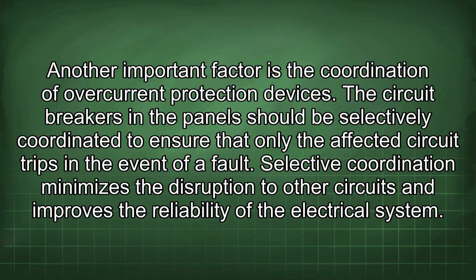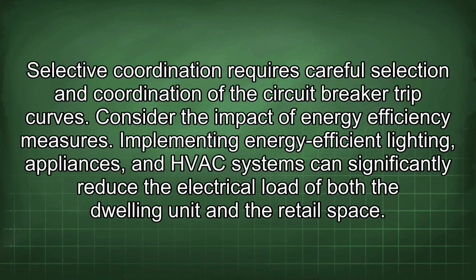Another important factor is the coordination of overcurrent protection devices. The circuit breakers in the panel should be selectively coordinated to ensure that only the affected circuit trips in the event of a fault. Selective coordination minimizes the disruption to other circuits and improves the reliability of the electrical system. Selective coordination requires careful selection and coordination of the circuit breaker trip curves.